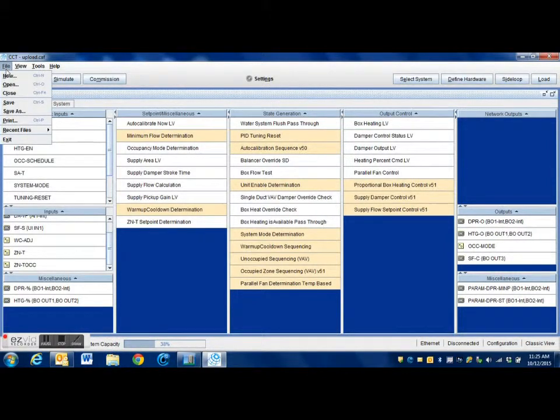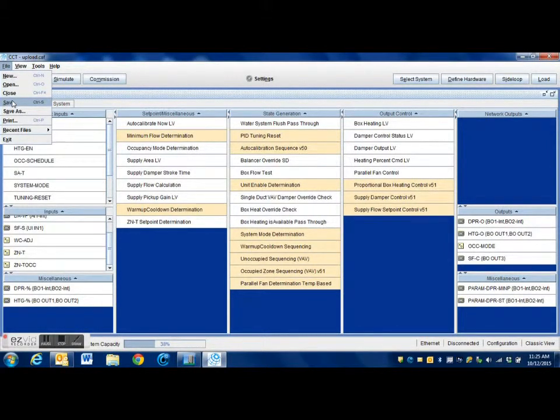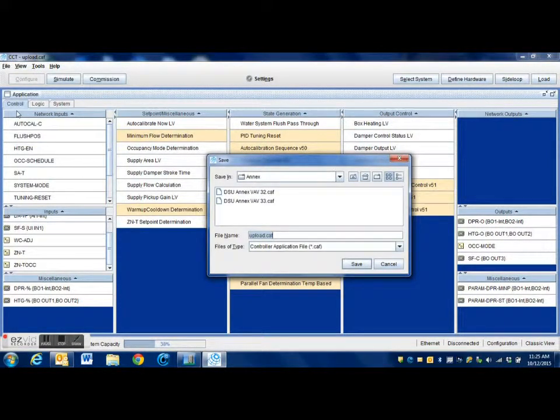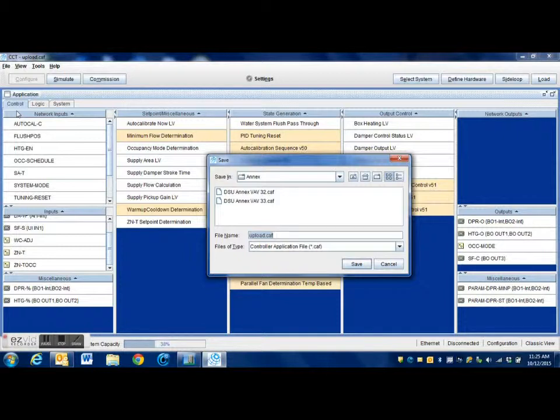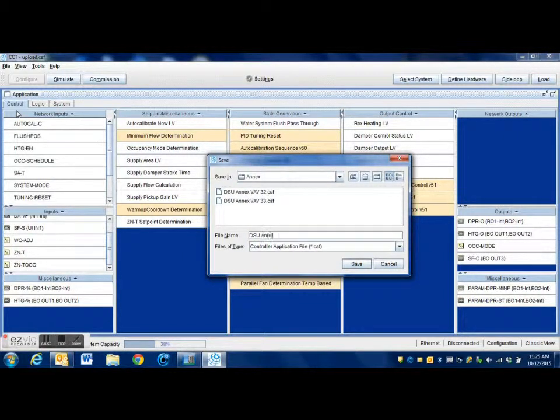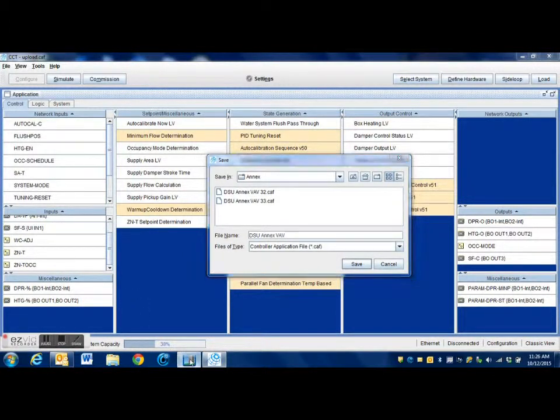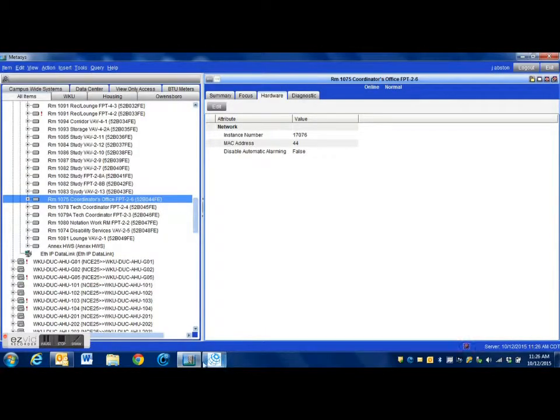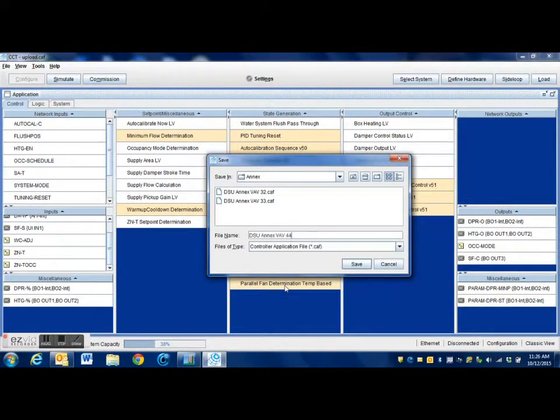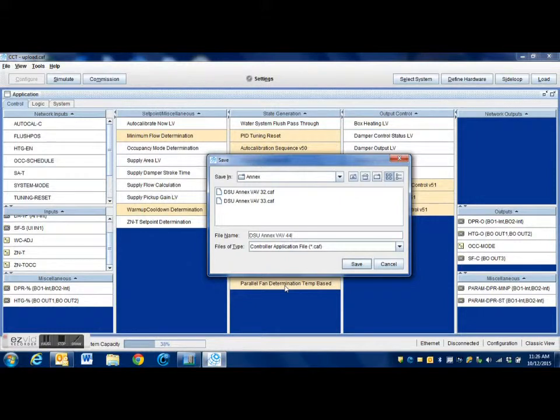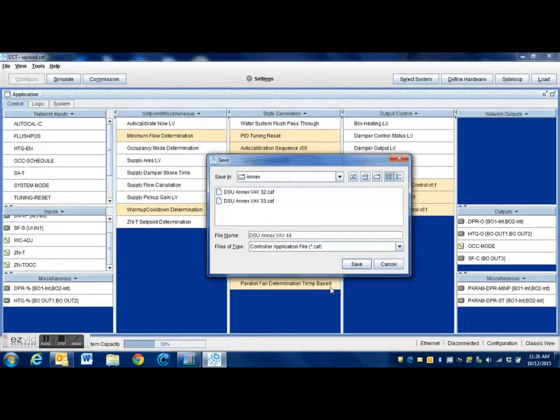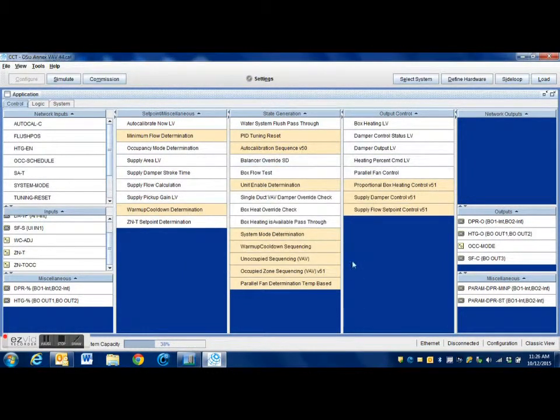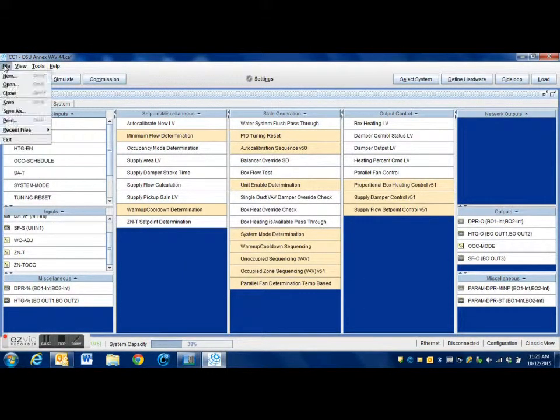Now we're just going to save this. I'll go up to file and save. I generally like to give the programs a very unique identifier. I will name them with the system name as well as the FC trunk if you're on a building that has multiple trunks. Then I also like to include the address for the particular VAV in that name as well. That way it cuts down on the confusion of whether or not a particular program is the specific one for the VAV that you're working with.